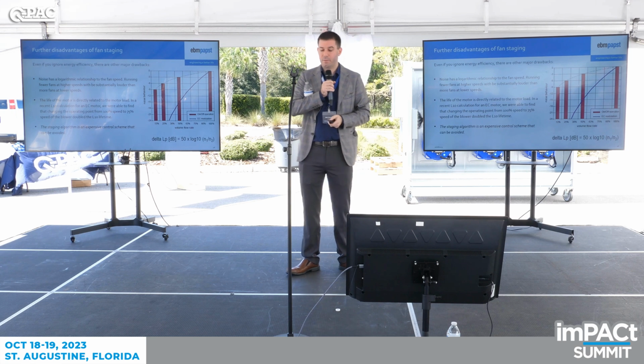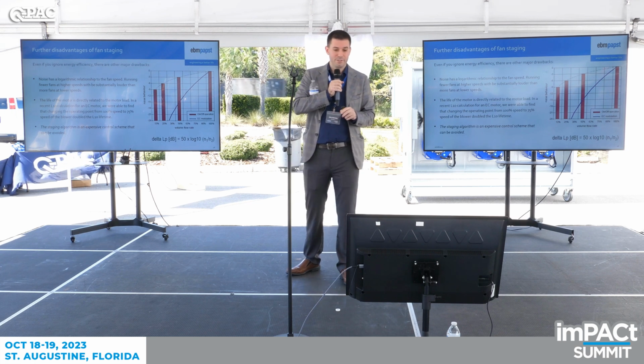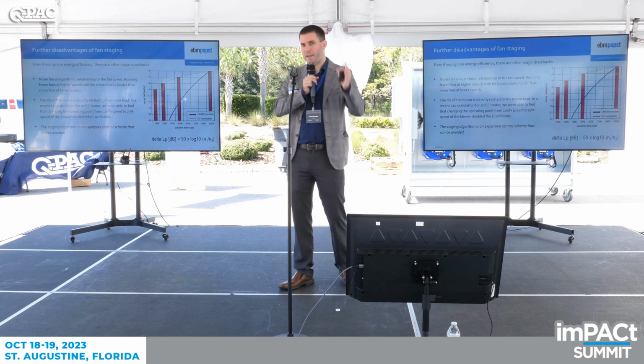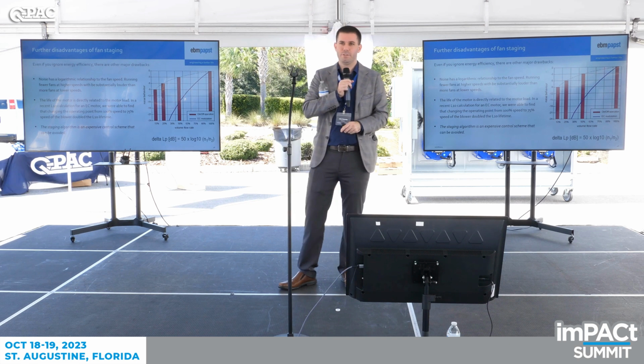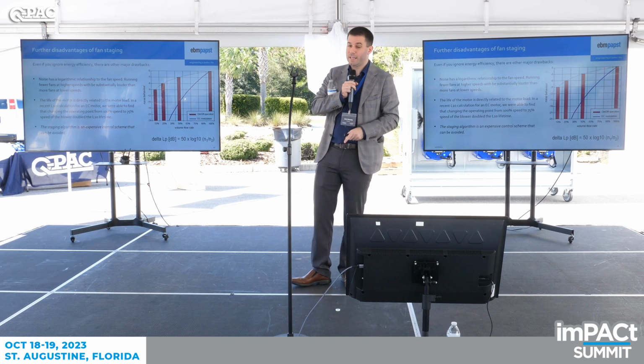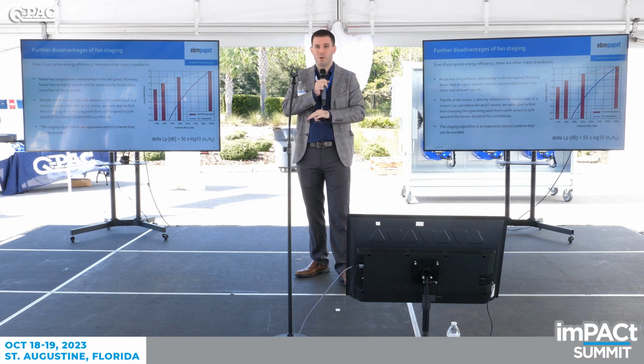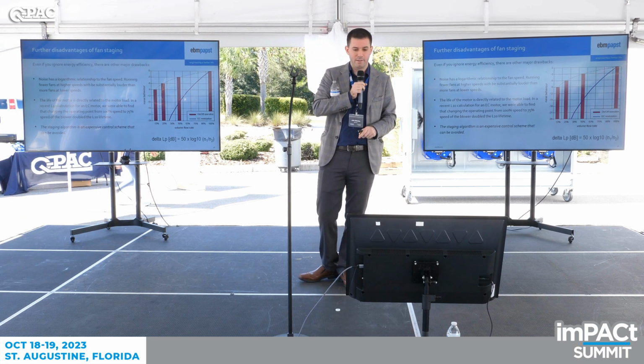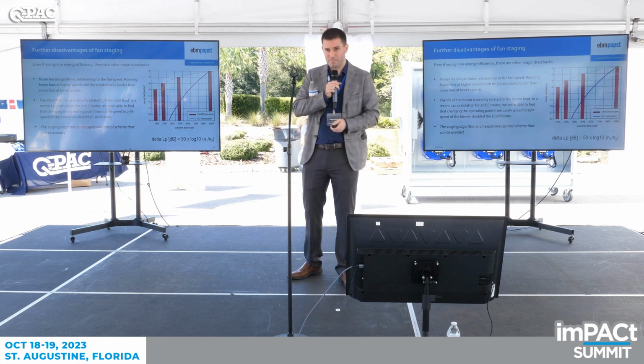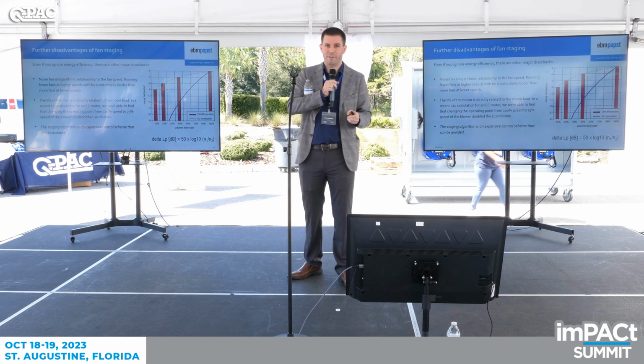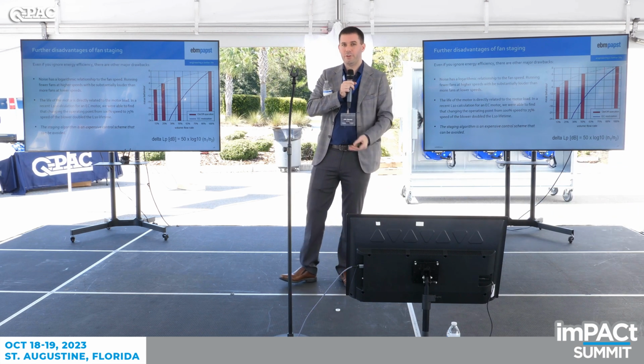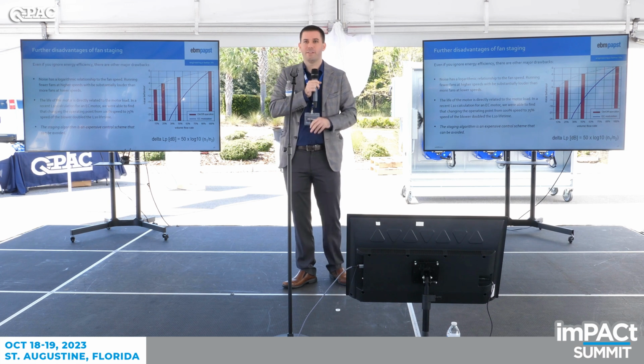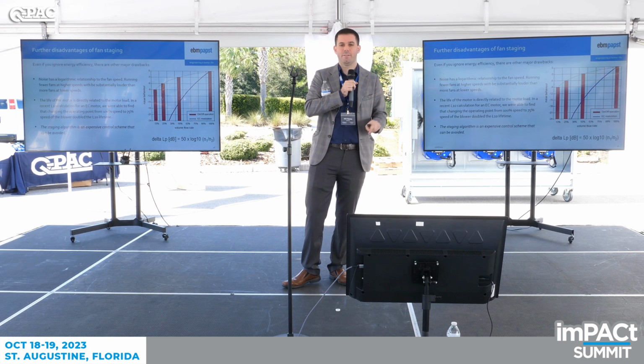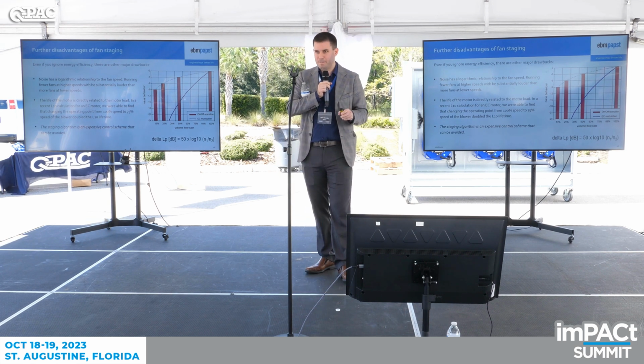Noise also is logarithmic to the speed of the fan. So if you had 8 fans and you shut off 4 of them, you saved 3 decibels. If you speed control all 8 fans down to 50% speed, you save 15 decibels. So it's a 12 decibel sound savings. You're still getting the same airflow. You're now at lower power, and you're going to get longer life out of all 8 of those fans. So it's something to keep in mind.